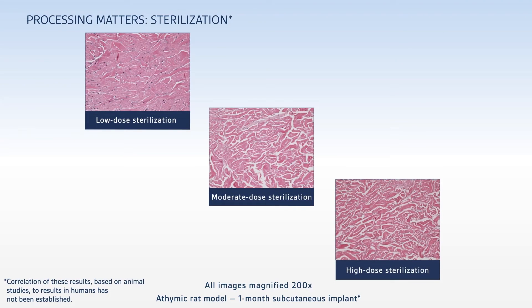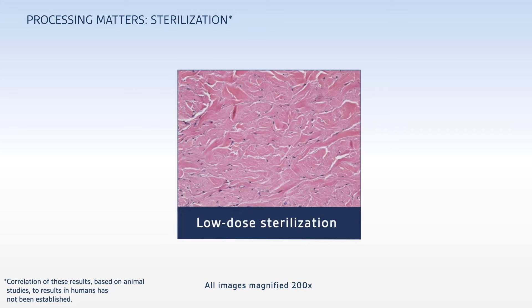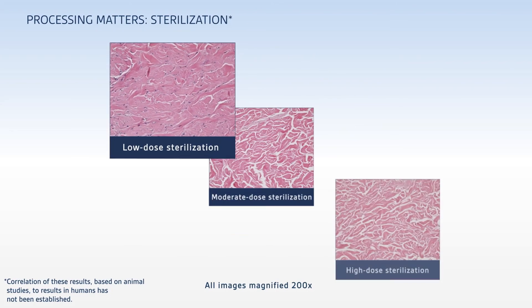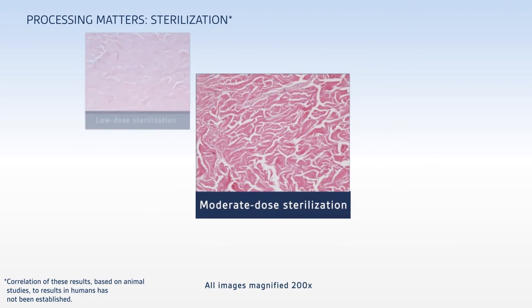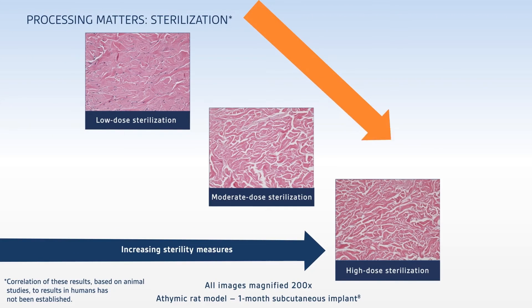It took a significant amount of time and effort to determine a sterilization dose that would give us the optimal balance of regeneration and sterility. These histologic images from a preclinical animal study compare the results of different irradiation doses after one month of implantation — we see some dose-dependent differences pretty clearly. Lower dose sterilization, specifically the E-beam irradiation used to terminally sterilize Alloderm, maintains the native dermal architecture and consistent host fibroblast infiltration, indicative of regeneration. But as the doses get higher, we see a noticeable change in dermal morphology, as well as a decrease in fibroblast cell infiltration into the matrix. So in these preclinical studies, as the sterilization dose increases, the host response becomes poorer.